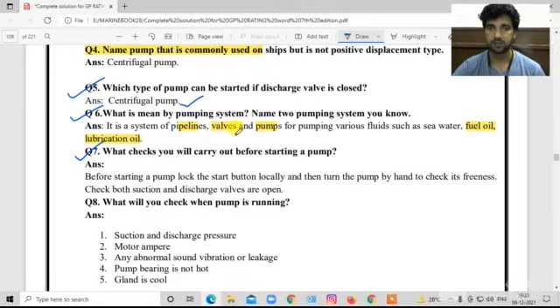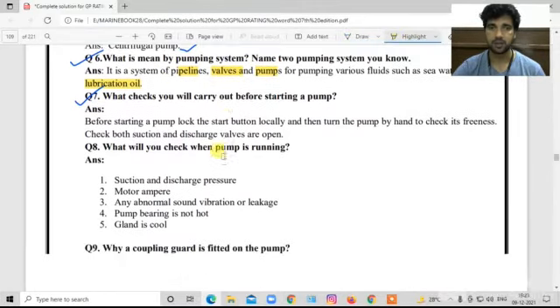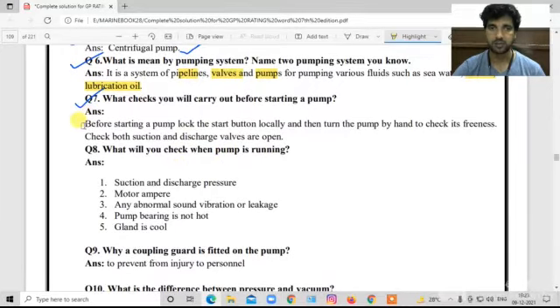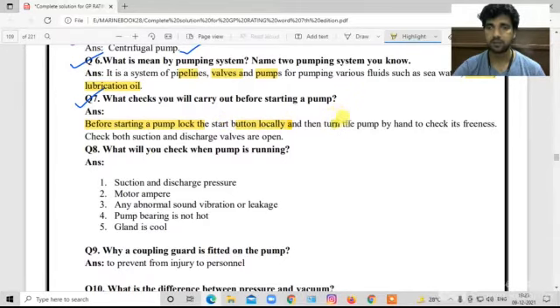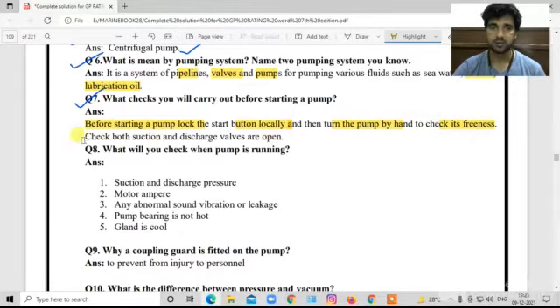What checks will you carry out before starting the pump? Before starting the pump: first, lock the start button locally; then turn the pump by hand to check it rotates freely; then check that both the suction and discharge valves are open.